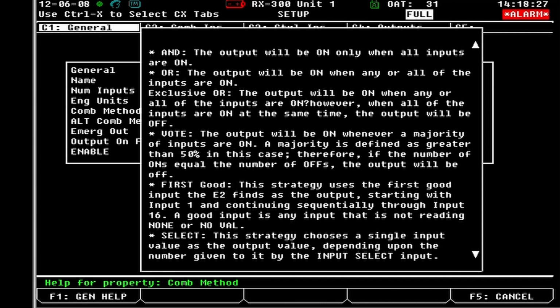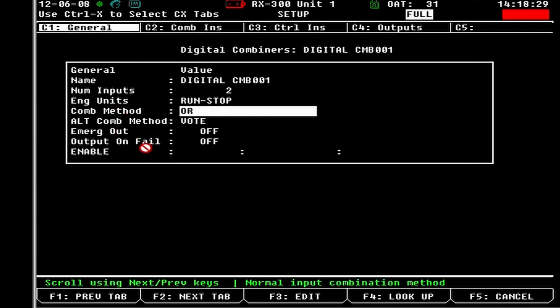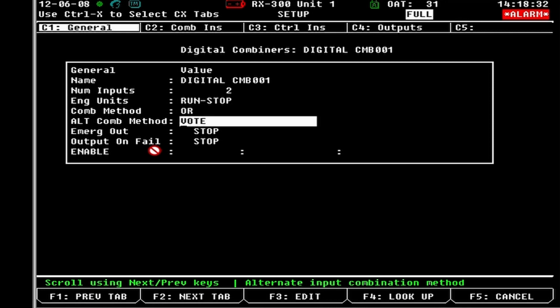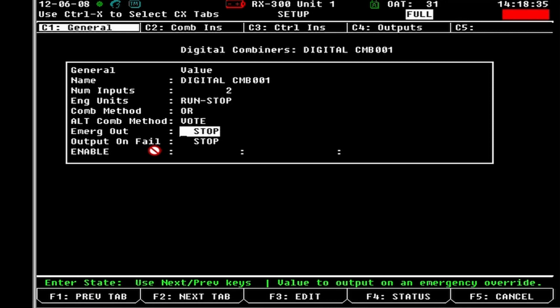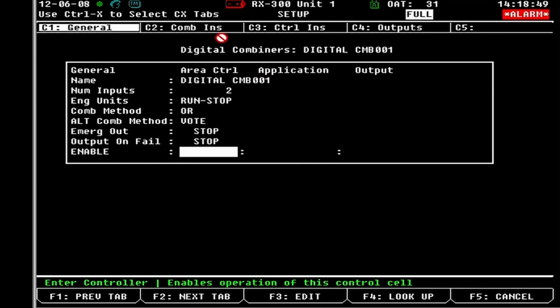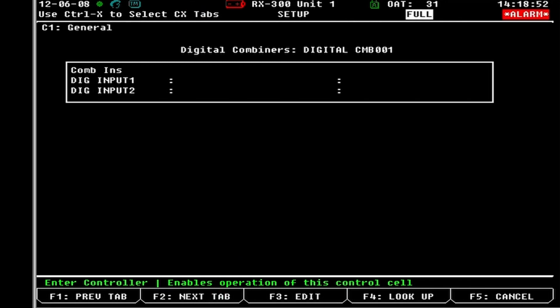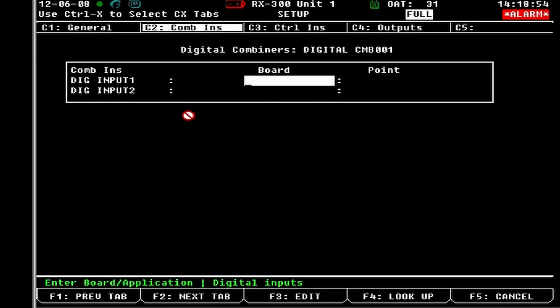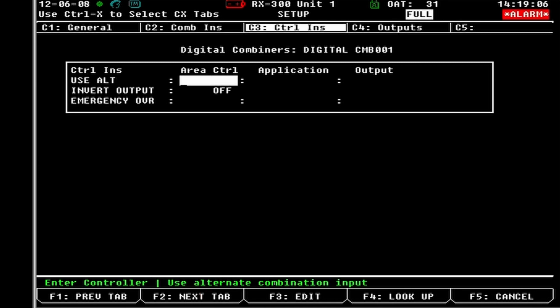So we'll click out of here. So just like everything else, you have an alternative combination method. You have an emergency out, whether it be stop, run, it's going to be whatever your engineering units are. You have an output on fail, so if this were to fail out, what the output was going to read. And then same thing, you have your enable. So inputs. So you have your digital inputs in. So you can do 16 on here. So if you had to combine a ton of inputs digitally, this is where you would do it. If you need more than 4.